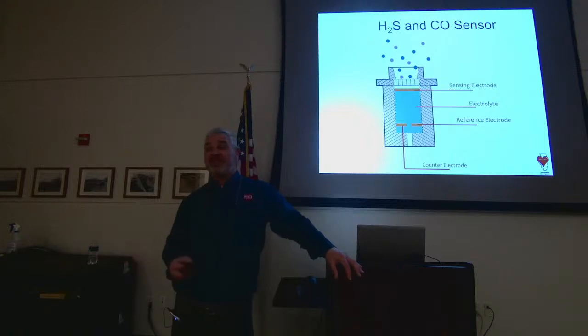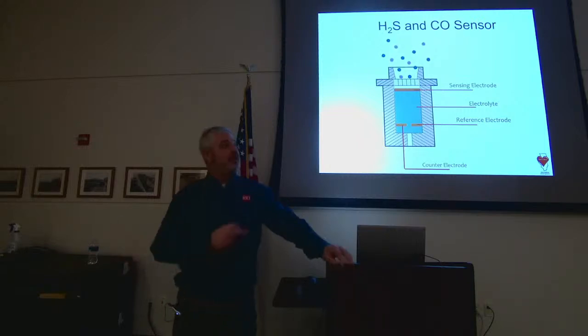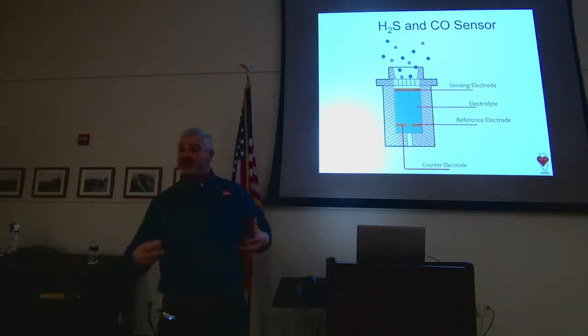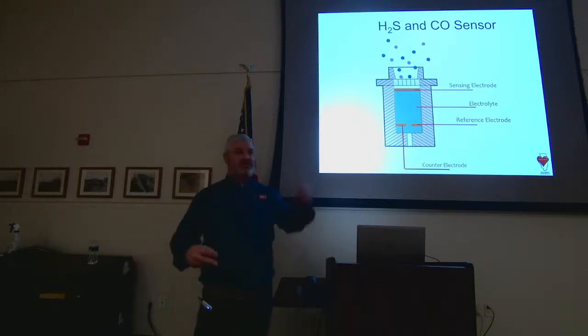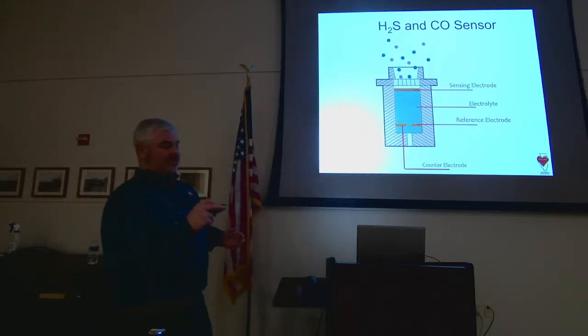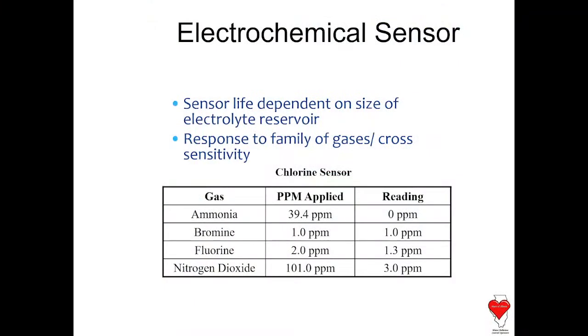How often do we see CO? More so than we see H2S. So then the general effect is your CO sensor will fail before the H2S. Why? Because it's not seeing it as often, we're not using as much of that fuel. So O2, CO, H2S, and that leaves us with electrochemical sensors and cross sensitivities and things like that. We take care of those with filtration, not really something to be concerned about in your applications.